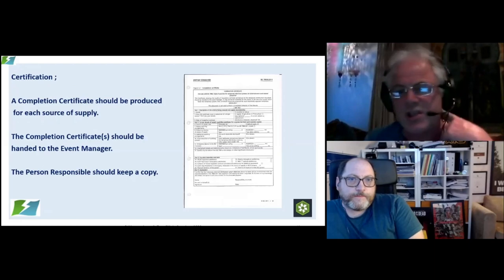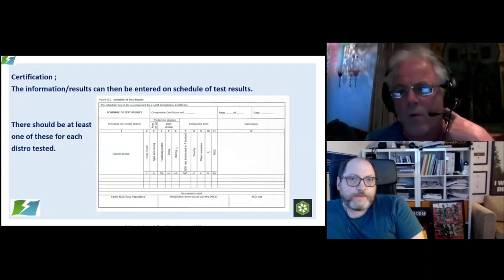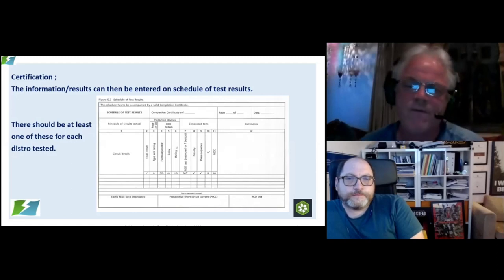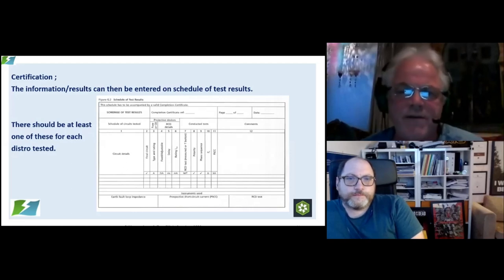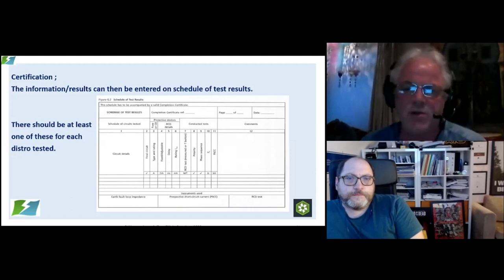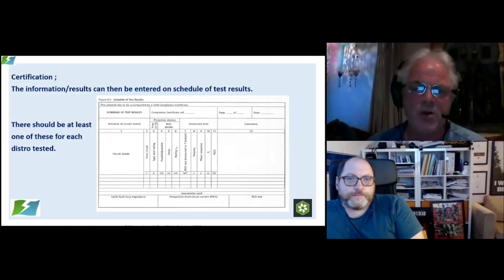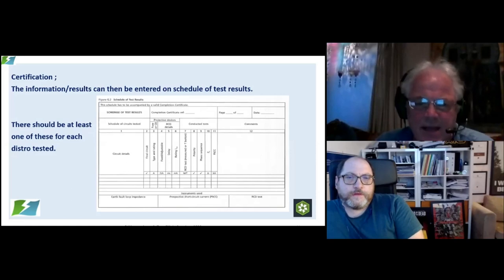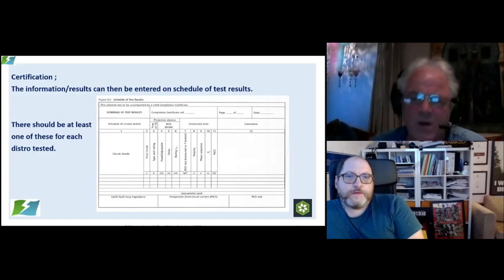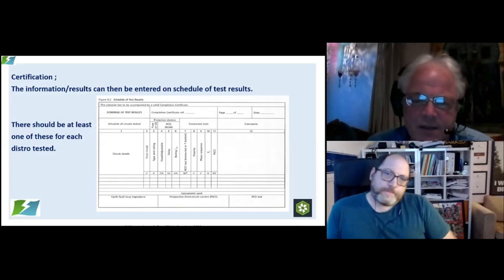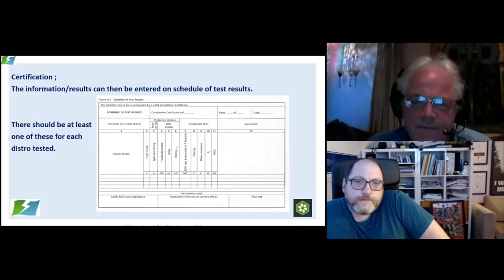This is a schedule of test results that we use for temporary installations. So you can see it's totally different to the schedule of test results for a fixed installation. This is taken directly from 7909, and you can adapt these and make your own up. The actual tests that are done there are fault current, done at the end of the circuit, the earth loop at the end, phase rotation, polarity, and then the rest of it is all to do with RCDs.